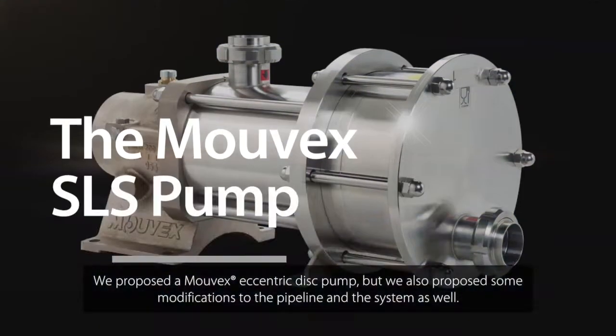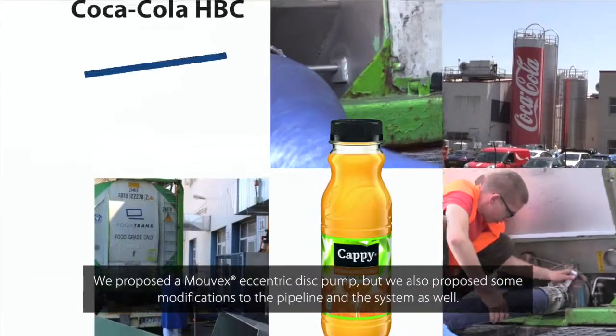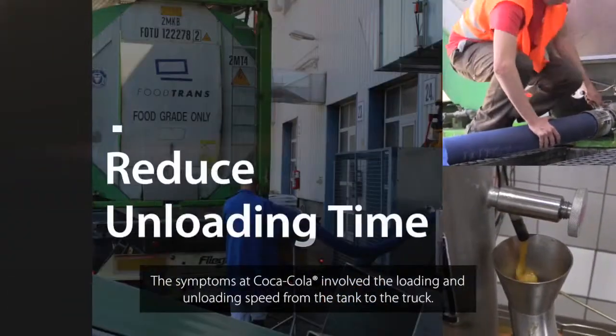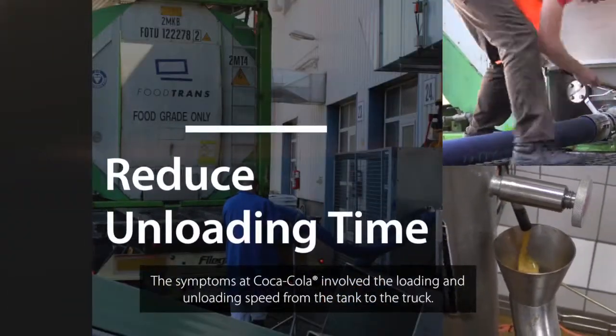We proposed a Mouvex eccentric pump, but we also proposed some modifications in the pipeline and the system as well. The symptoms at Coca-Cola were low unloading speed from the tank and the truck, and the second issue was cavitation, which caused vibration and noise.